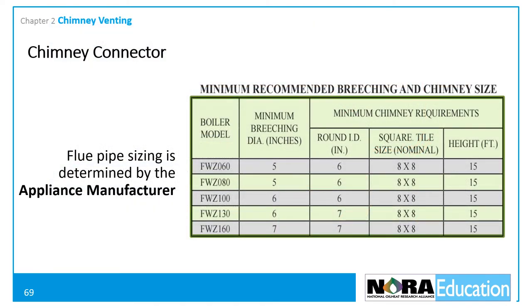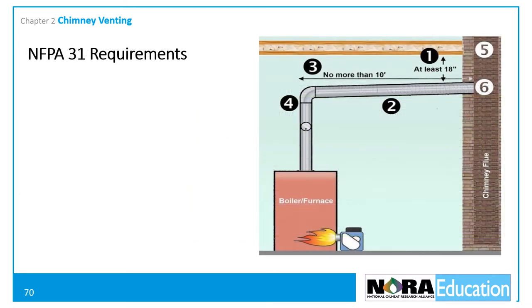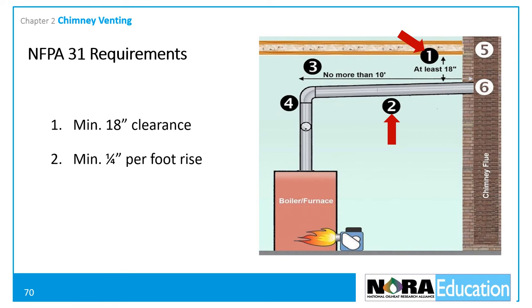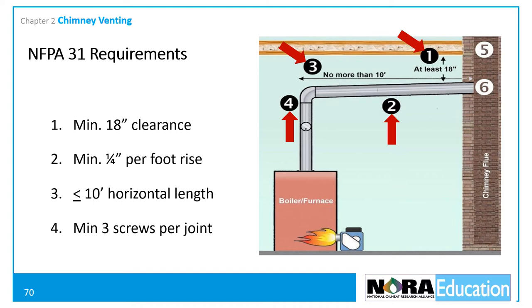Flue pipe sizing is determined by the appliance manufacturer. A manufacturer chart shows minimum flue pipe size ranging from 5 to 7 inches depending on the model. NFPA 31 has numerous regulations regarding the connection between the appliance and the chimney. Technicians should refer to the current edition of the standard and the local authority having jurisdiction. The 2020 version of NFPA 31 requires for natural draft appliances: the flue pipe must be at least 18 inches from a combustible wall or ceiling; the flue pipe must maintain a pitch or rise of at least one-quarter inch per foot of horizontal length; the horizontal length must not exceed 10 feet unless a draft fan is used; and each joint of the flue pipe shall be fastened with at least three screws.